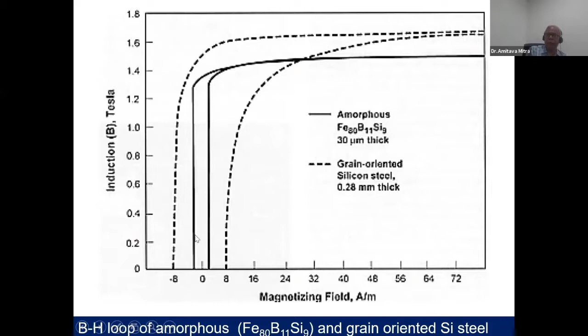What we can get in this case is around 1.4, but there is an abnormal decrease in the area of the hysteresis loop. If we plot this curve compared to regular grain oriented or high grain oriented silicon steel versus amorphous or metallic glasses, there is a drastic difference in the energy loss, that is the area of the hysteresis loop. This is the hysteresis loss, this is the classical eddy current loss, and this is the excess eddy current loss. This loss is reduced because the amorphous alloy has high resistivity.